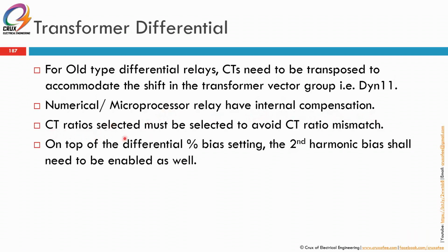So even the CT ratio must be selected to avoid CT ratio mismatch. But with new relays, you can compensate these CT ratios if there's a mismatch, so you will minimize the error due to the CT ratio mismatch. But with old relays, you cannot compensate. So you have to really select the ratio correctly, and the error is much higher as compared to the new modern relays.